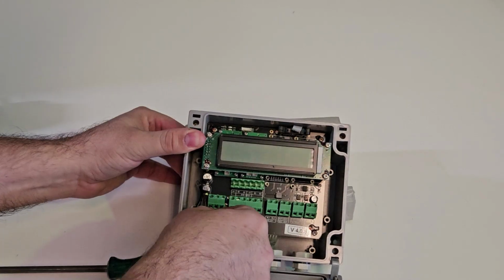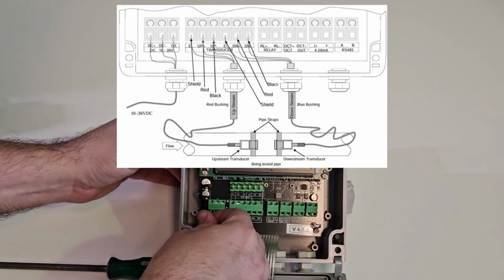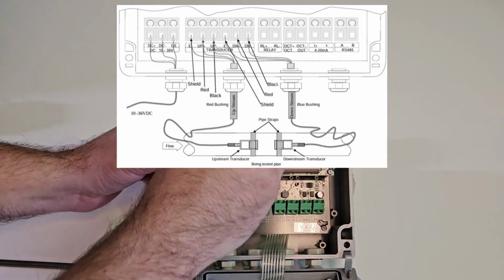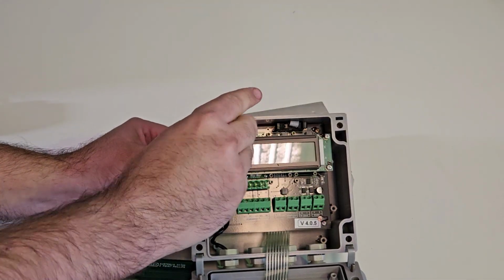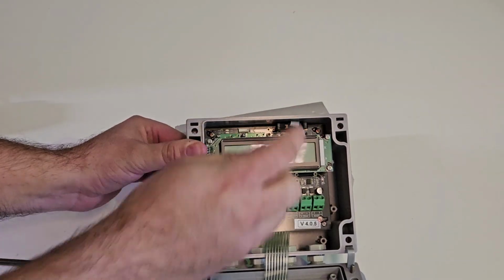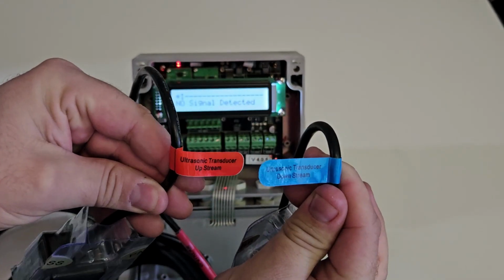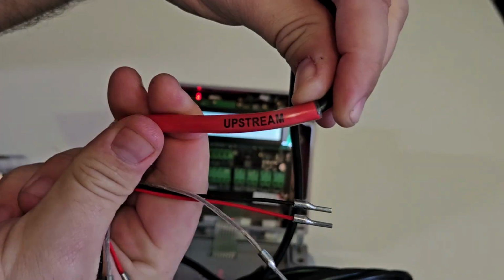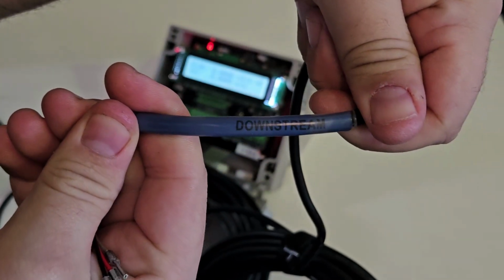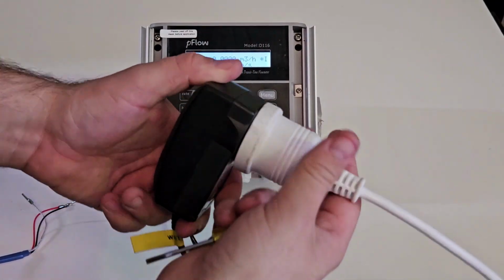Insert the positive and negative power wires and tighten down the terminals. This wiring diagram shows the typical layout. But always refer to the markings on your physical device in case of change by the manufacturer. Now take the sensor cables and observe the labels and markings. Ensure the power for the flow meter is off.